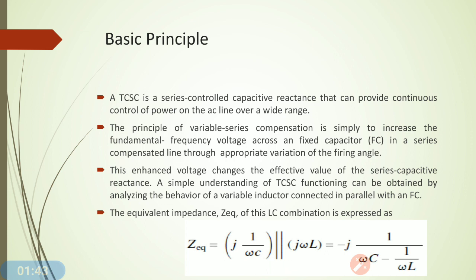A TCSC is a series controlled capacitive reactance that can provide continuous control of power on the AC line over a wide range. The basic principle of operation of TCSC is variable series compensation, which simply increases the fundamental frequency voltage across the fixed capacitor by controlling the firing angle of the Thyristor Controlled Reactor. This voltage changes the effective value of series capacitive reactance, allowing us to change various parameters of the transmission line.